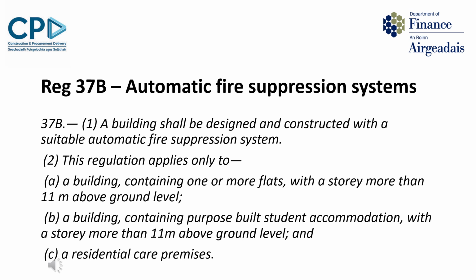So the regulation is about recognising the effective role sprinklers can play in saving lives and preventing injuries. Sprinklers control fire spread and fire size, allowing additional time for residents to escape and for the fire and rescue service to respond. Requirements on this issue vary across England, Scotland, Wales and the Republic of Ireland. Requirements for each jurisdiction are generally based on research commissioned over the last 20 years by the English, Welsh and Scottish governments, the Chief Fire Officers Association, and carried out by the Building Research Establishment, BRE. So this new regulation brings the position here on automatic fire suppression systems provision closer to those other jurisdictions.